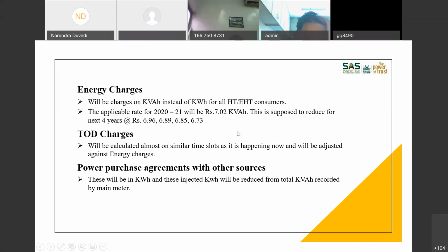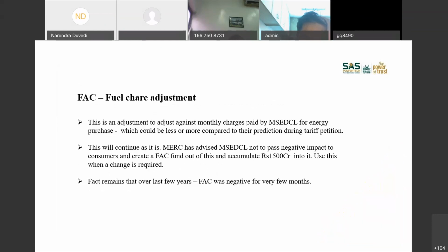in the next 5 years. TOD charges, again, as I said, the time slots are the same and the calculation method is also the same. The only thing is they will use kVAh instead of kWh for calculating it. Power purchase agreements also, this will be in kWh, and this injected kWh will be reduced from the total kVAh recorded by the main meter. So if you keep your kWh equal to kVAh, even under PPA, you will end up paying less for whatever you take from the utility company apart from your PPA. So that also, actually, the provision remains the same.